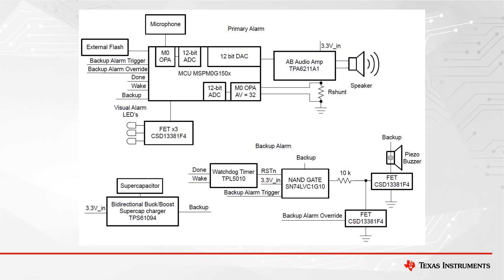This system also allows for the MCU to trigger an alarm override when desired. The external watchdog timer provides additional redundancy, resetting the MCU in case of software hangups. The external flash option allows for larger audio files to be played as well. Additional safety features such as speaker fault detection are accomplished by measuring the current of the speaker amplifier. An external microphone option allows for another way to ensure the proper operation of the primary alarm speaker. This system can be controlled from a standalone host or act independently. An integrated real-time clock on the MSPM0 also adds extra value to the system.